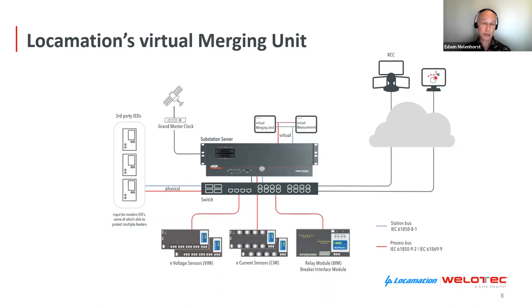As you can see in the schematic setup, the voltage and current interface modules, called VIM and CIM, are connected to a commercial off-the-shelf network switch. The interface modules publish sampled value streams based on the IEC 61869 standard. The virtual merging unit itself runs on a substation server, which is a substation-hardened commercial off-the-shelf industrial computer, and the VMU software provides calibration and adjustment of the process data. The published sample value streams are then ready to be used by other third-party IEDs and/or future virtual applications running on the same substation server.